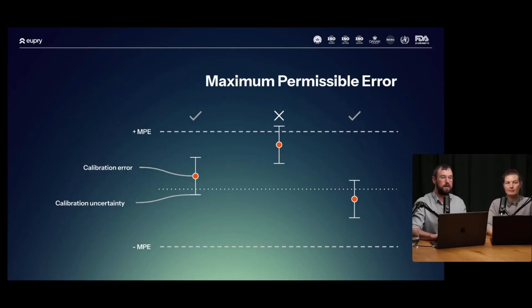So in the first example here, what we can do is set what we call an MPE, and an MPE is a maximum permissible error. That's the largest error plus uncertainty that we can accept, and that means that we know that whenever it passes the MPE, the maximum uncertainty and error is within this MPE. A great example is cold storage. We'd often choose an MPE of 0.5 degrees. And that means that if we have a calibration error of 0.25 degrees and an uncertainty of 0.25 degrees, we're just at the limit. But if this goes outside our maximum permissible error, we cannot guarantee that the instrument measures within the tolerances anymore.